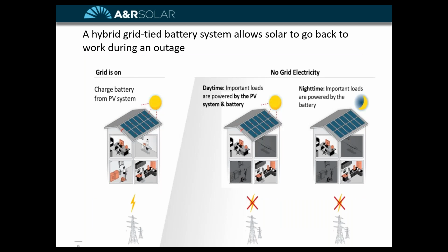We're talking about hybrid grid-tied battery systems that allow solar to go back online during an outage. Today, if you have solar with no battery and the grid goes down, your solar system will shut down automatically. It has to, by National Electric Code, to protect line workers from us back-feeding power onto the grid. So your solar system synchronizes to the voltage and frequency on the grid, and once synchronized, it supplies power to the home. Any excess flows out to the grid and you get a credit for it.